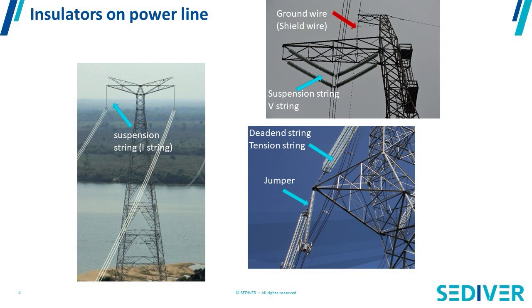The picture at the bottom shows you another configuration of insulator strings. Sometimes when you look at the tower you see that there are horizontal strings. If you follow a line you will see that every five, six, or seven or ten towers, depending what the line is, you will find a tower stronger, and you will see that the metal structure of the tower itself is more robust and with insulator strings which are horizontal. These horizontal strings are called dead-end strings and also sometimes called tension strings.